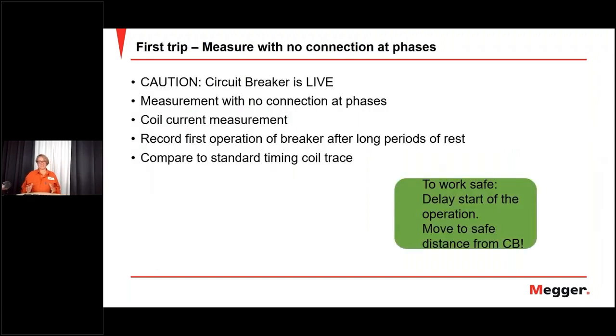We have been talking about these classical measurements and also now this DRM, but we also promised to mention ways to measure the circuit breaker without having connections directly at the phases. We have one measurement type, which is called first trip, which is made with normal circuit breaker analyzers, but you need some accessories. But you have to be really cautious here. The circuit breaker is live. You need to have power in the station to be able to measure the first trip. You do the measurement without connections at the phases, so you don't have to access those.